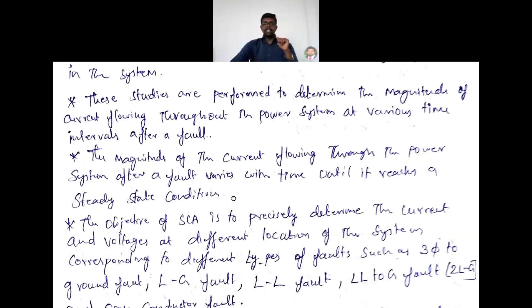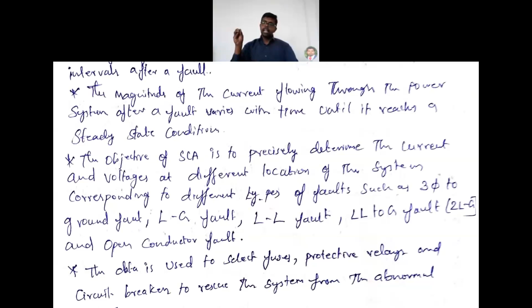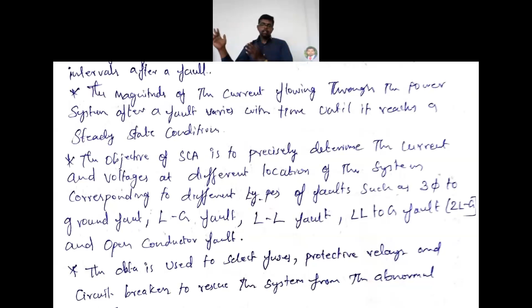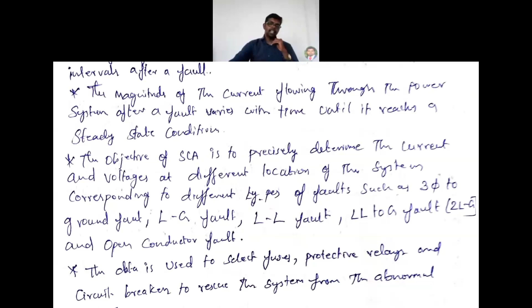The objective of short circuit studies is to precisely determine the current and voltage at different locations of the system, for example from the substation to some point 2 kilometers away. If a fault happens there, such as a line to ground fault, what might be the current increase? Similarly, line to line fault, double line to ground fault, or open conductor fault - we analyze all these cases.